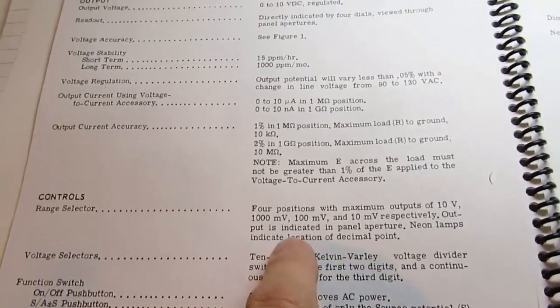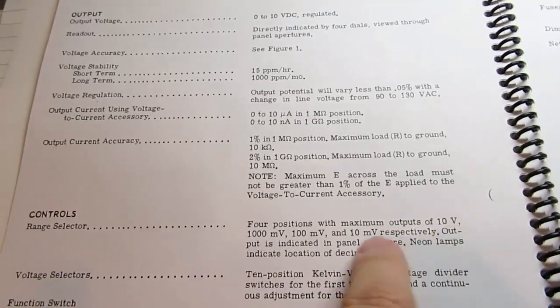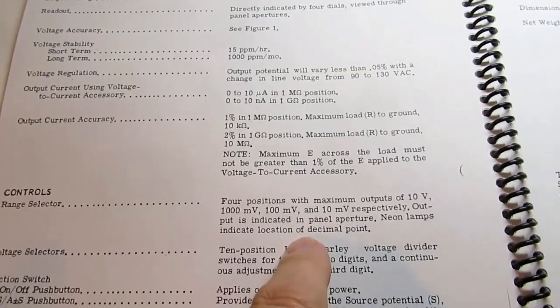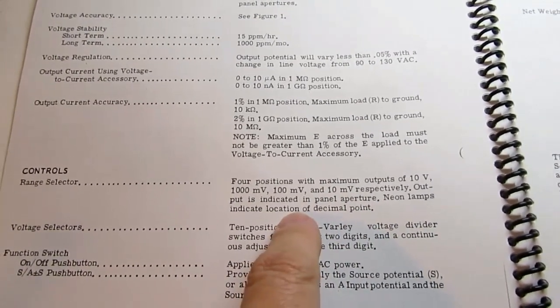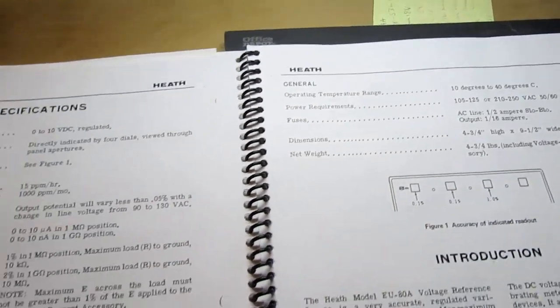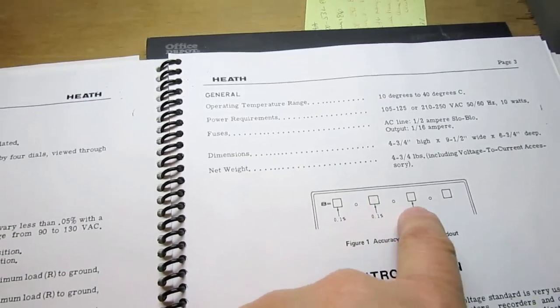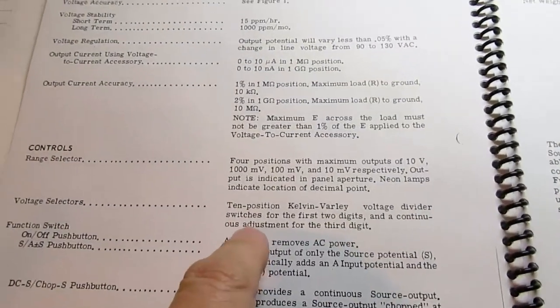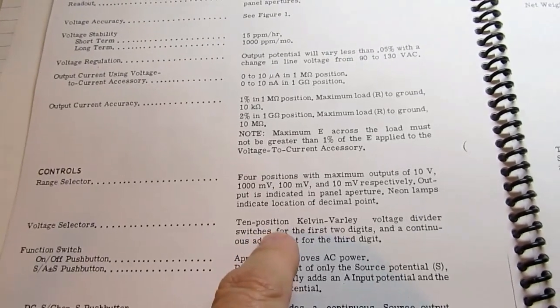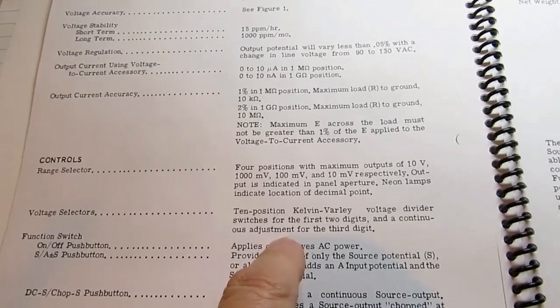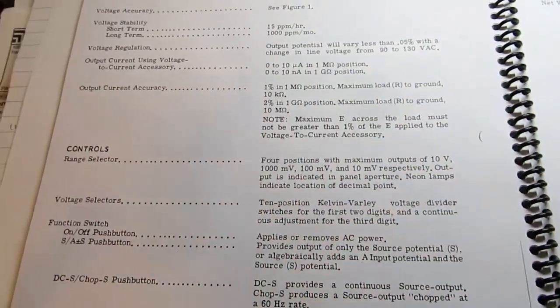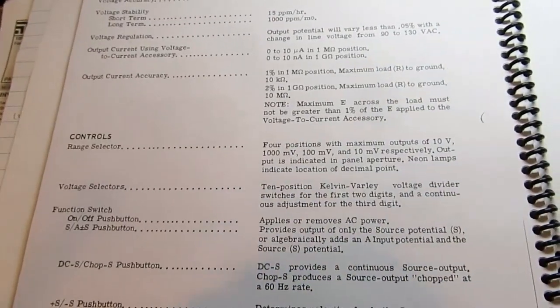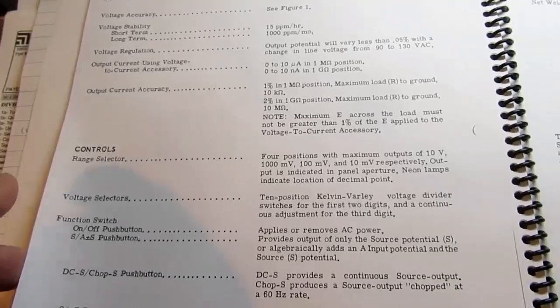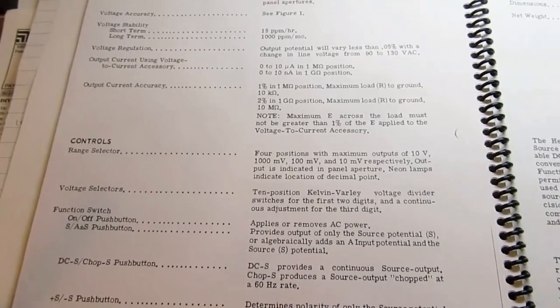Output accuracy, we've already talked about that to some degree. The four ranges are 0 to 10 volts, 0 to 1000 millivolts or 1 volt, 0 to 100 millivolts, and 0 to 10 millivolts. Neon lamps indicate where the decimal point should be out of the 3 digits and the range. The voltage selectors use 10 position Kelvin-Varley voltage divider switches for the first 2 digits and continuous adjustment via potentiometer for the 3rd digit. There are additional switches, just like on the other voltage reference that I already did a video on, the older version of this product really.